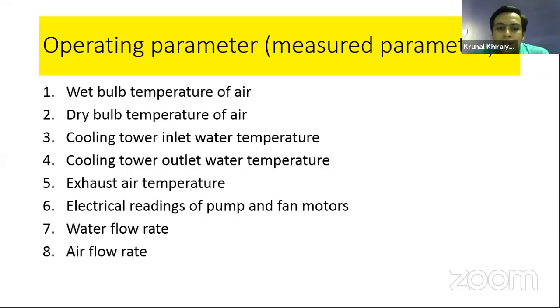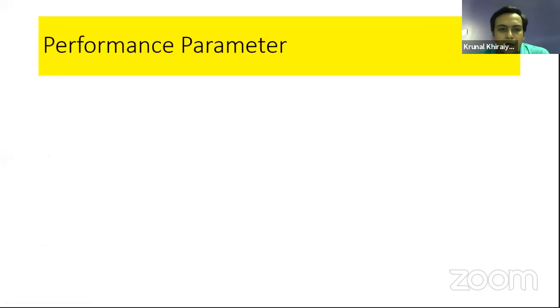Now airflow. How do you measure the airflow rate? Please, audience, respond. Orifice. Okay, manometer, yes, correct. Anemometer, yes. An anemometer is used for measuring the velocity of gas in a particular duct with the help of area. As all of you know, Q, the rate of discharge, equals area into velocity. So by using the anemometer, you can measure the velocity of the air and get the airflow rate. I think all of you are clear how to measure and what the different parameters required for performance assessment are.